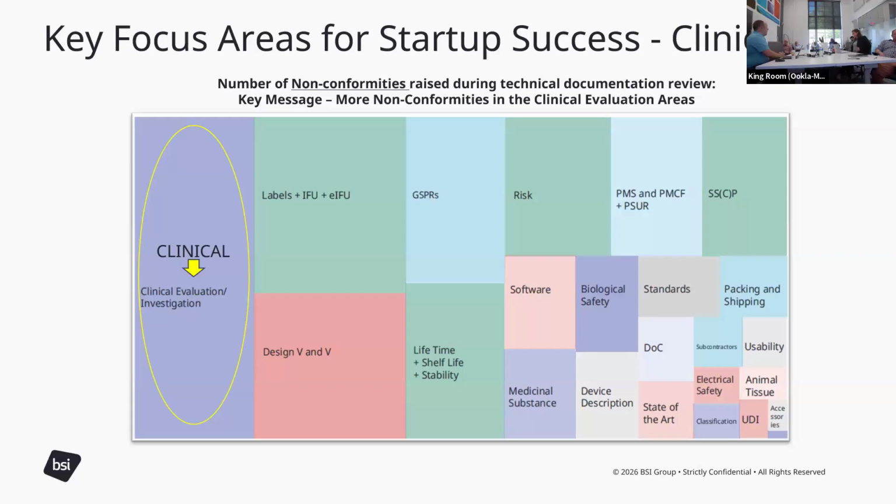Yeah, so a good one and pretty relevant to Memphis: orthopedic implants went from not very regulated in Europe to hyper-regulated, where everything's on a product certificate and you need a lot of clinical data. It's going to potentially switch, for things like the fracture plates and the bread and butter ortho devices, to what we would call well-established technology. And you would not need clinical data for that type of device.